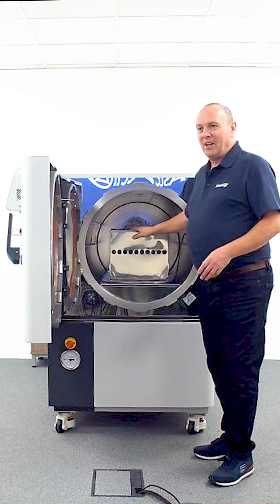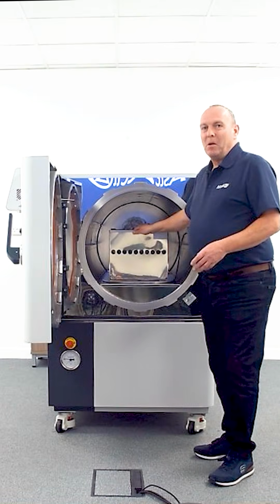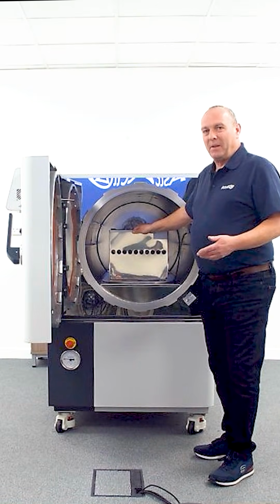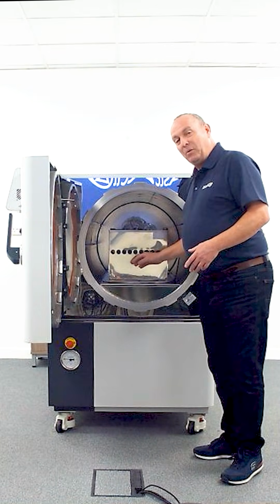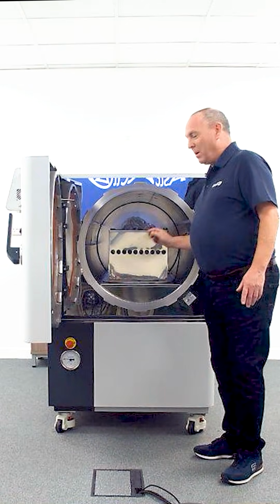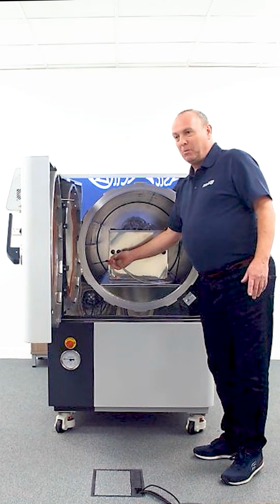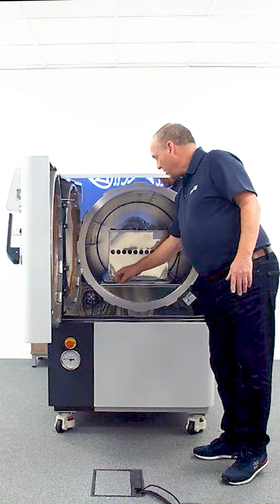At the end of sterilisation, obviously the machine will cool down, but this time it will cool down quicker than the media load, because it's only looking at the temperature of the chamber rather than the temperature of the load probe, because it's not being used. So it will cool down faster, and the fans will kick in earlier to help bring the load down to a safe temperature where the machine will open.